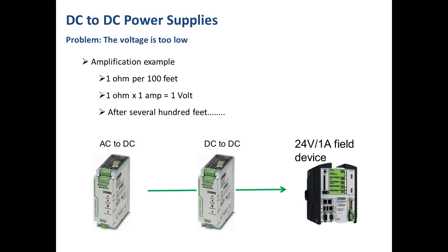Amplification is another common functionality for DC to DC. This functionality is required when there are long runs of DC wiring. As an example, using a 24-volt field device that draws 1 amp and wire with a rating of 0.01 ohms per foot, there will be a 1 volt drop for every 100 feet of wiring. As the wire run approaches 500 feet, the voltage drops to 19 volts where it connects to the field device. This voltage can be amplified using a 24 to 24 volt DC to DC to accept the 19 volt input and provide a solid 24 volts DC out to ensure the reliability of the DC bus.